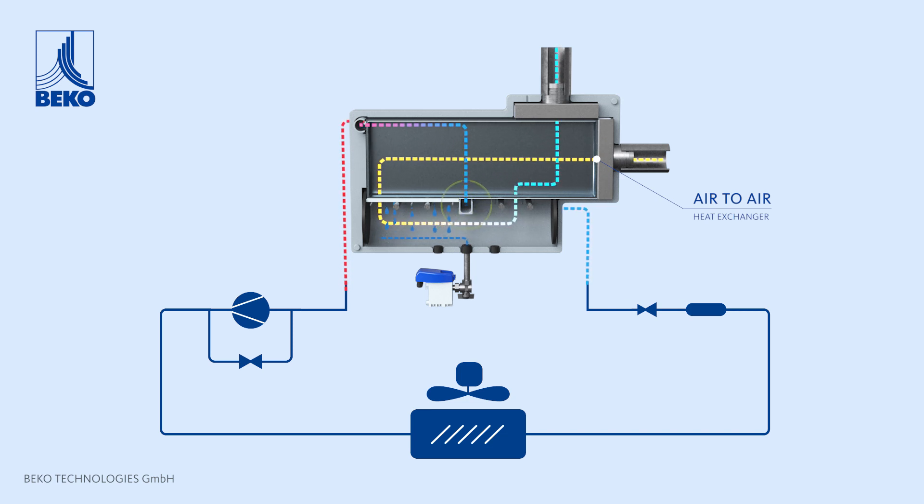compressed air enters the unit and is pre-cooled in the air-to-air exchanger. The compressed air is then cooled in the air-to-refrigerant heat exchanger to the required pressure dew point. Accumulated condensate is discharged from the dryer via a true zero-air loss BEKOMAT condensate drain.